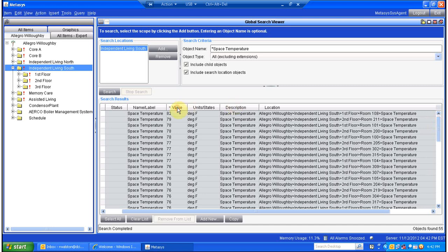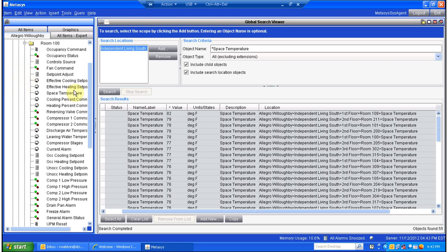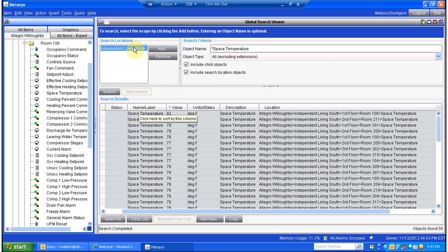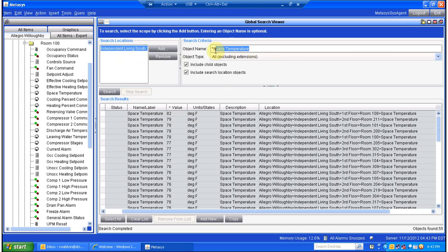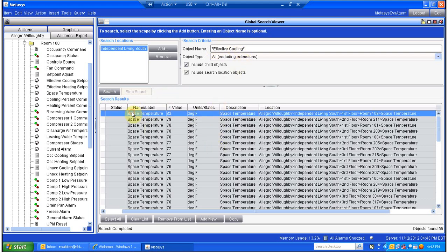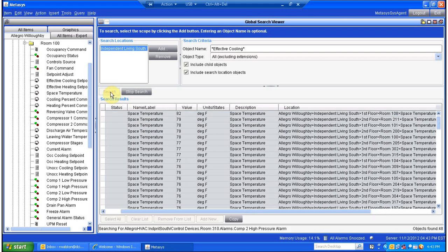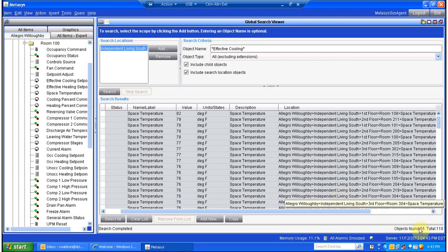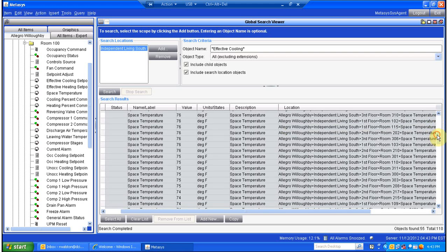That's just a quick view of how to use the basics of the global search viewer function. Now let's say we want to compare space temperature with space set point so we can better define what is functioning out of range and what is not. We're going to select the effective cooling set point. We've already got Independent Living South in our search location, so I'm just going to change this to effective cooling, use the asterisk again — so anything that has effective cooling in the title will be brought into my list. Hit the search button. It found an extra 55 items for a total of 110, and it automatically populates those items to the bottom of the screen.